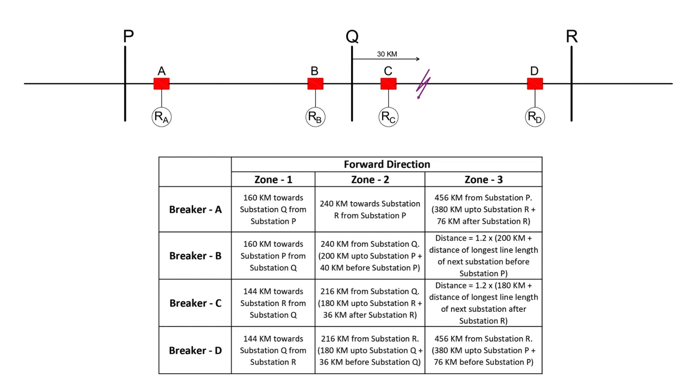Now, let's say there is a fault on the QR line located 30 kilometers from substation Q. Relay C will detect this as a zone 1 fault and trip immediately. Relay D will sense the fault as a zone 2 fault, but it won't trip immediately. Instead, relay C will send a direct trip signal to breaker D, ensuring it opens without delay.